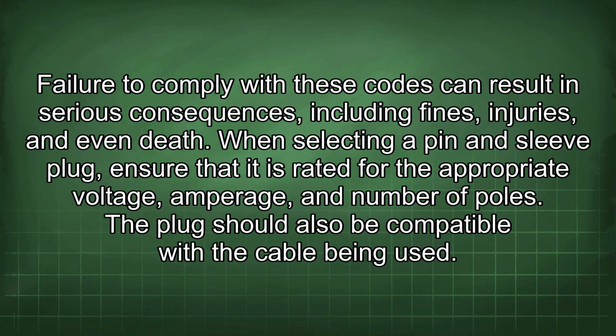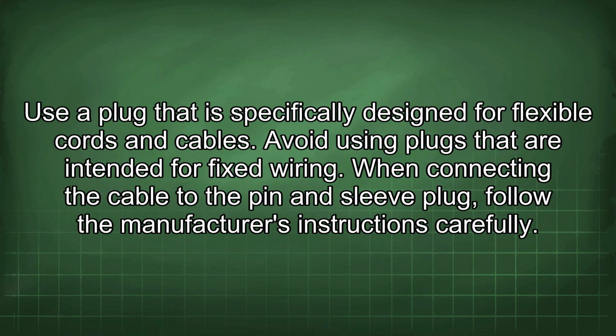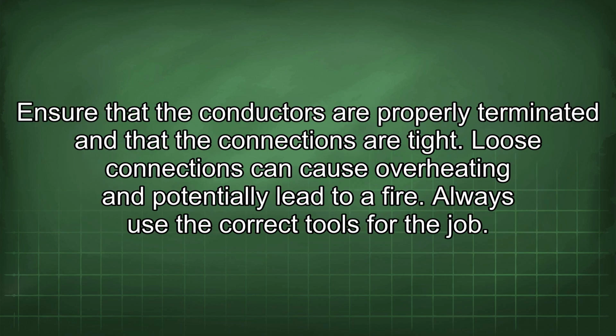When selecting a pin and sleeve plug, ensure that it is rated for the appropriate voltage, amperage, and number of poles. The plug should also be compatible with the cable being used. Use a plug that is specifically designed for flexible cords and cables. Avoid using plugs that are intended for fixed wiring. When connecting the cable to the pin and sleeve plug, follow the manufacturer's instructions carefully. Ensure that the conductors are properly terminated and that the connections are tight. Loose connections can cause overheating and potentially lead to a fire.